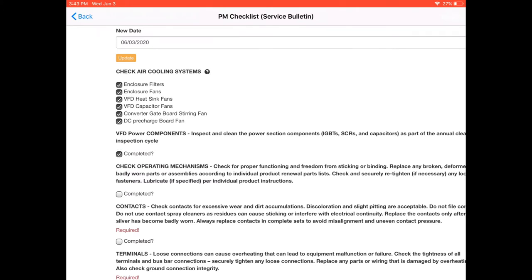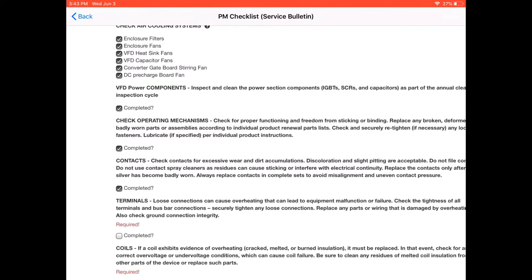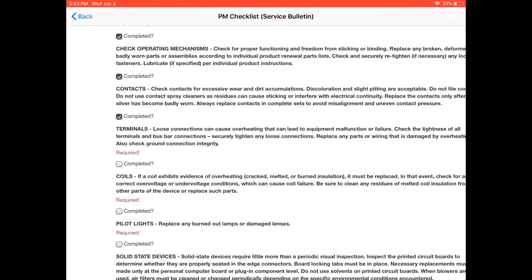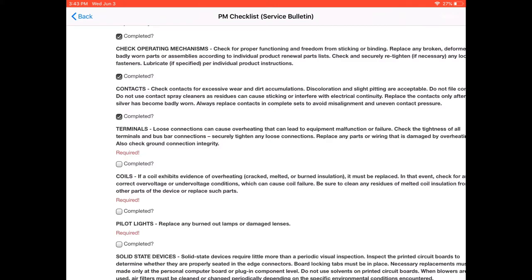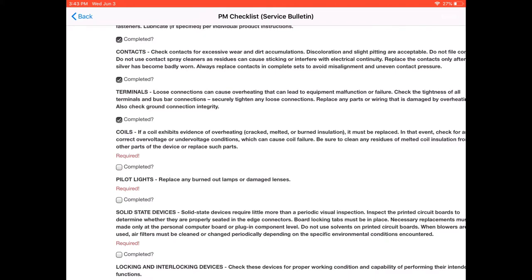Next thing is to check the operator mechanisms in the control panel. We check the contacts on contactors and relays for example. Check all the terminals, power and control, to make sure that they're tight to manufacturing specifications. Check the coils and all the control relays. Make sure there's no burning or discoloration.